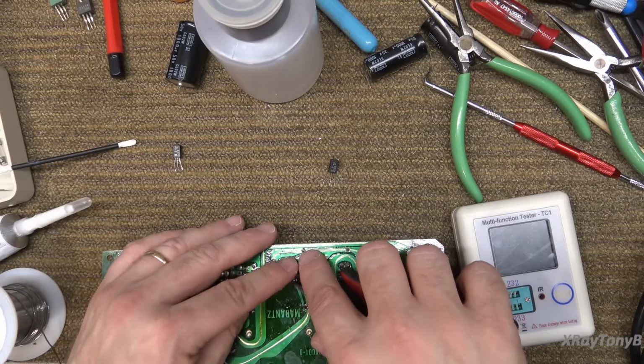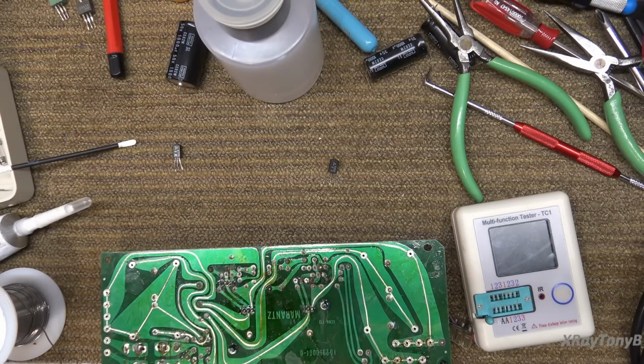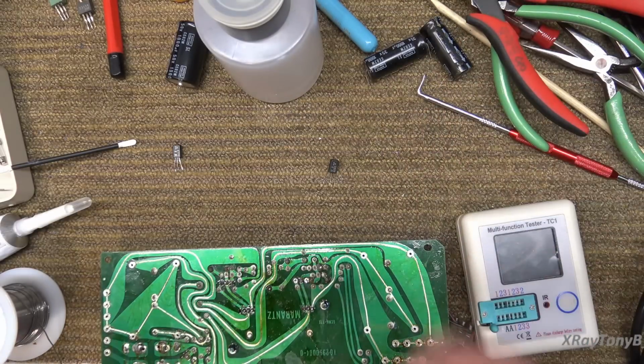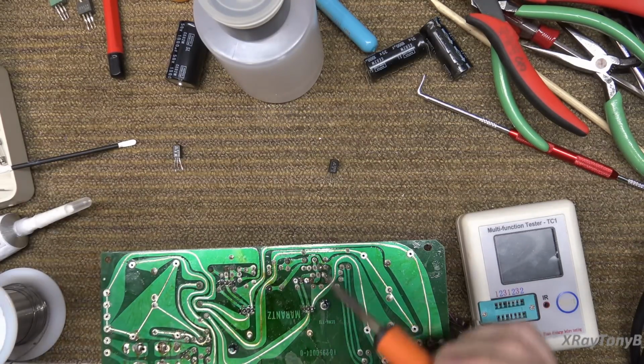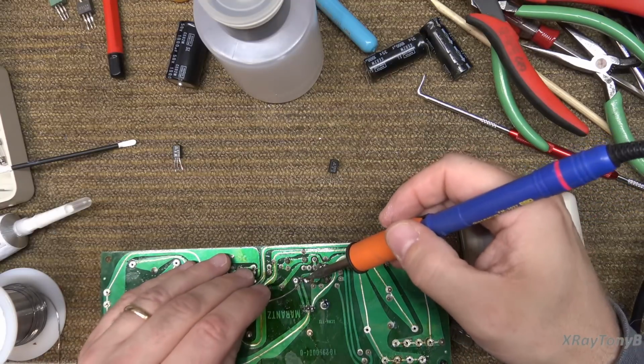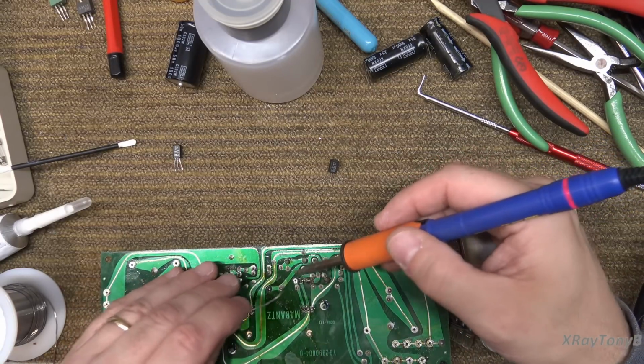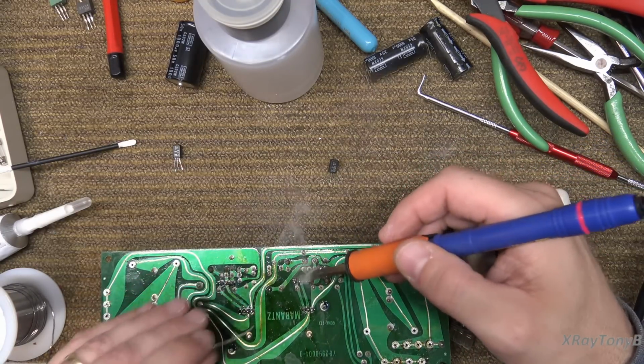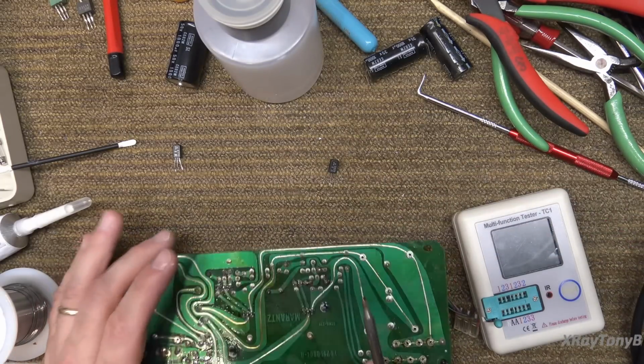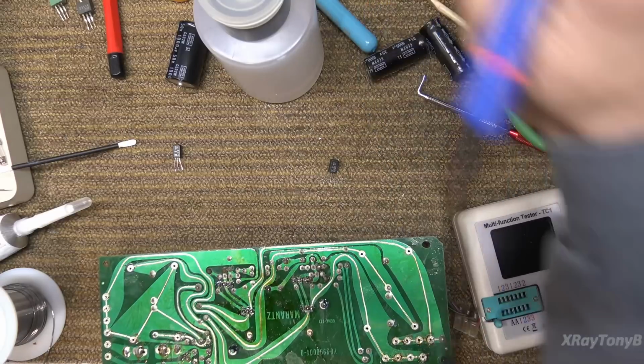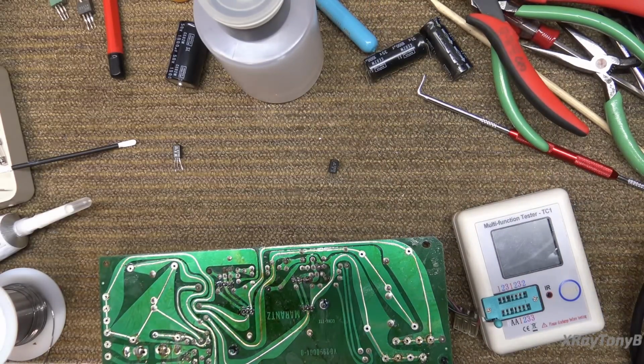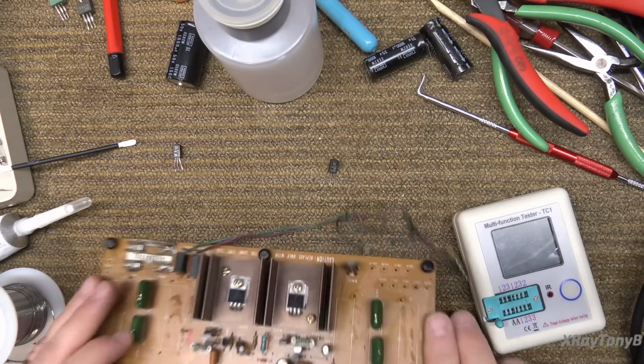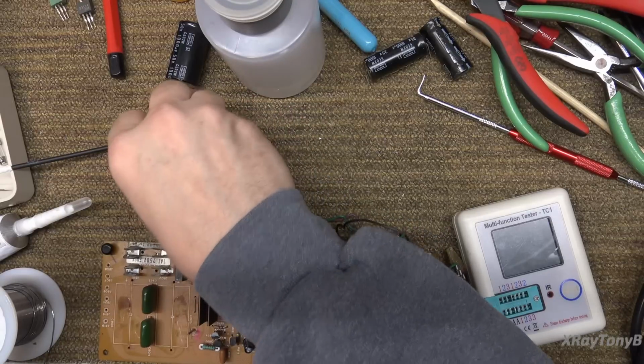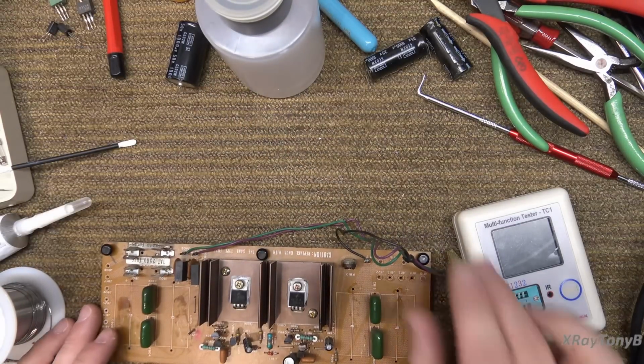I've only known one person that ever got directly hit. Because of all the interlocks that these machines have, it's very hard to get shocked by that, the primary voltage like that. Or not the primary, that's a different thing, but the actual power that's across the X-ray tube. But one person got it in their hand and it arced out the back of their elbow, and it literally blew their elbow out. It's very ugly. Not anything to play with.